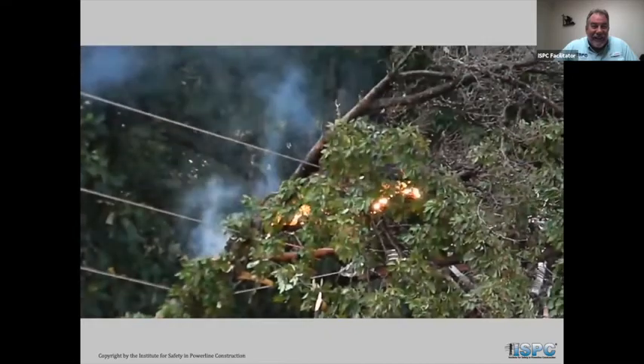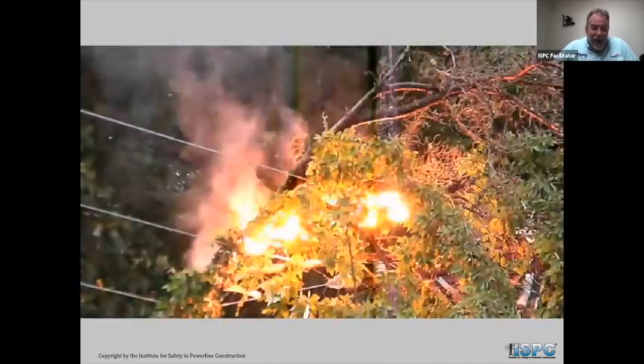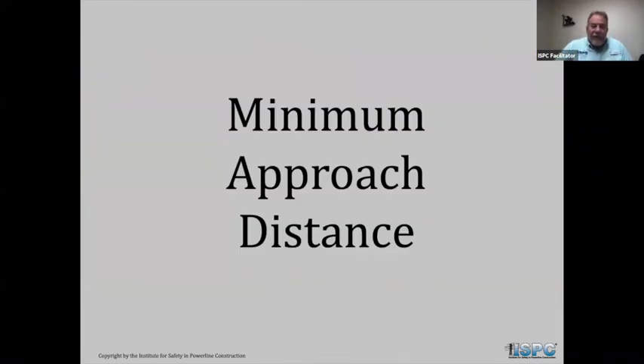The big question I usually get here is how come it didn't trip out? Well, again, we're not creating enough fault current for that recloser to see, but we did create enough heat that it eventually burned the line down. Gets a little confusing there. We did create enough heat to actually burn the line down so that the recloser did finally see it when it went phase to phase, and it opened up. However, if the conductors laid on the ground were not in contact with each other, that recloser could very well come back on again and energize that line. So that's when people really get injured, assuming that when a line falls on the ground, it's no longer energized, but that's not the case in most instances.